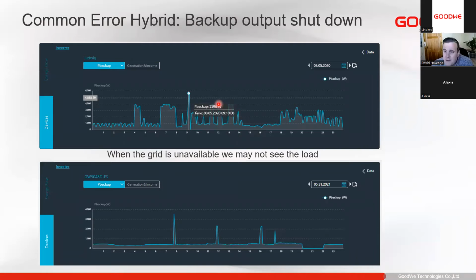However, when the grid is not available, the overload time is generally a lot shorter. With the grid available, we can overload up to 6.9 kilowatts, and it's dynamic. So if it's only 4.8, 5 kilowatts, it might allow it to run for an extended period of time, as this one probably ran for a minute or two before it shut down at 5.5.